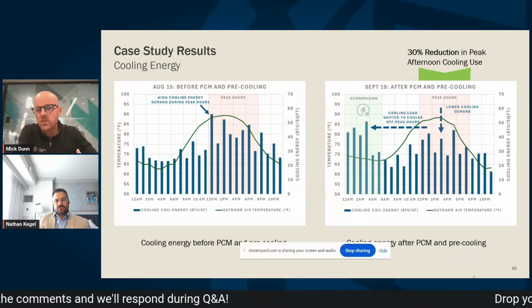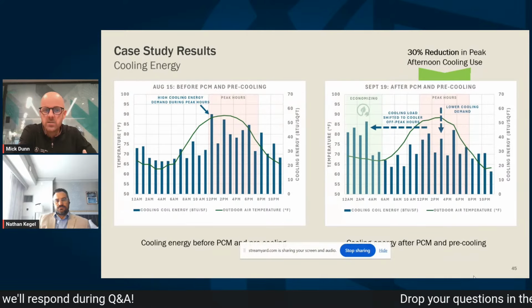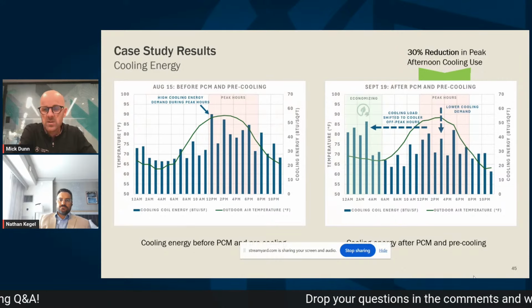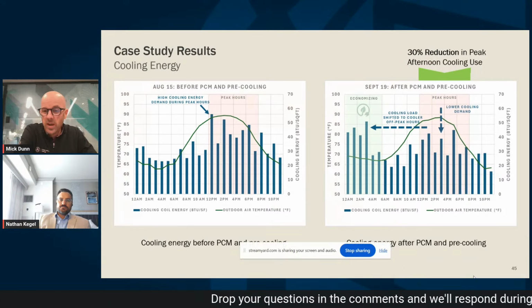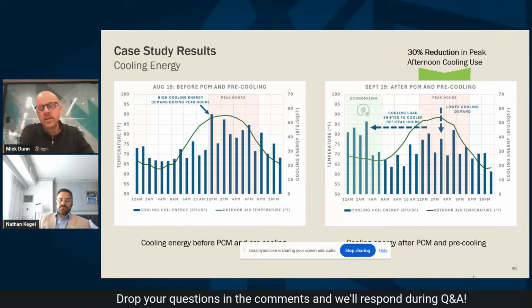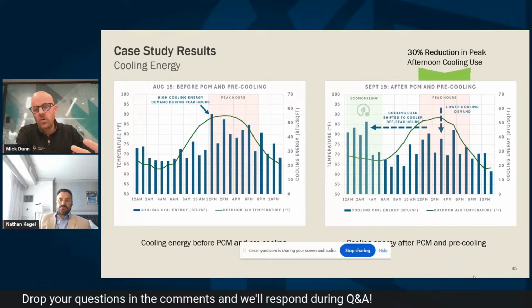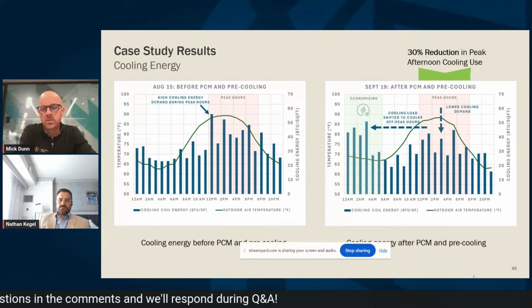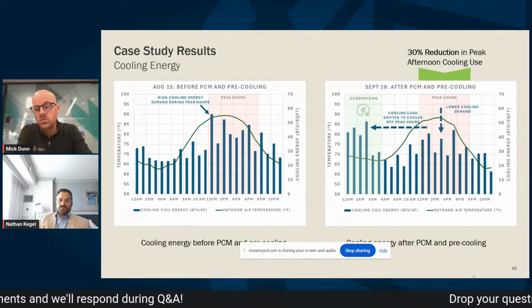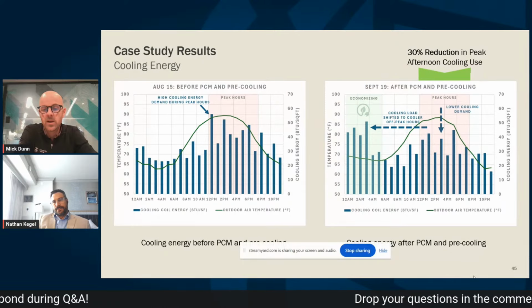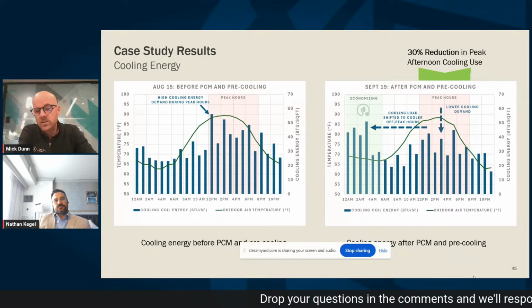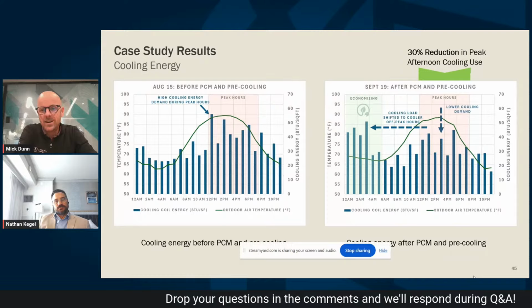We're seeing more energy being used in economizer cycle, so that would induce more fan energy, not as much chilled water in chiller energy. So there's an increase there on the coil, and then there's a decrease in the afternoon. So really the idea there is we're reducing chiller energy in that afternoon peak. And in this case, we're seeing up to a 30% reduction in that peak.